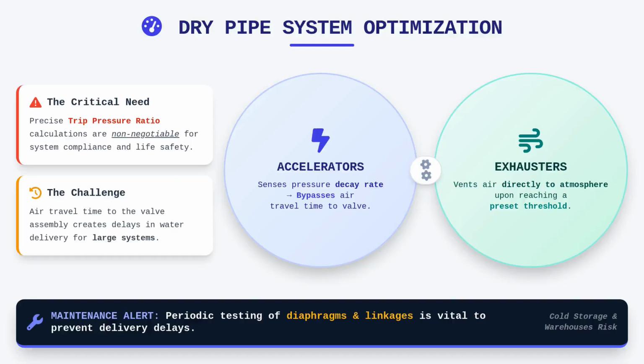Physics dictates the behavior of the compressed gas, and accurate calculation of the trip pressure ratio is non-negotiable for system compliance. To expedite the water delivery process in large systems, engineers frequently rely on quick-opening devices, such as accelerators or exhausters. An accelerator senses the initial rate of pressure decay and triggers the tripping of the dry pipe valve, essentially bypassing the time required for the air to travel back to the valve assembly.